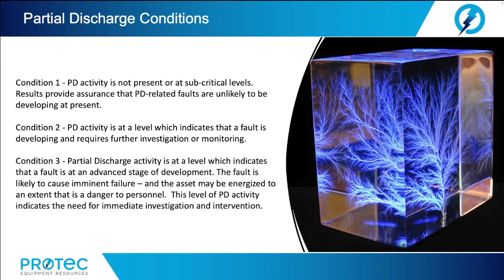Condition 3: partial discharge activity is at a level which indicates that a fault is at an advanced stage of development. The fault is likely to cause imminent failure, and the asset may be energized to an extent that is dangerous to personnel. This level of partial discharge activity indicates the need for immediate investigation and intervention.